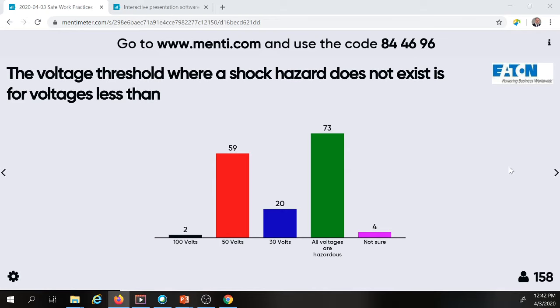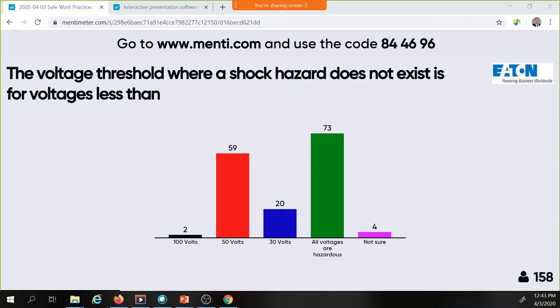So the right answer was 50 volts. For those of you on the web, on YouTube, you can see the answer there was 50 volts. For those of you on WebEx, I'm going to share that back over to look at those. We had 59 say 50 volts, and 73 said all voltages. I could possibly be in that all voltages are a hazard for a lot of different reasons, but 70E does recognize 50 volts and less as an area where you don't have to worry about a shock hazard. Again, that's just because of how much voltage is present to push current through the body.